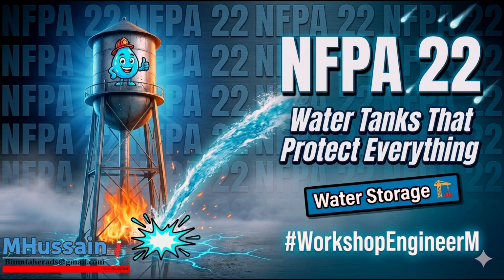Let's calculate the physical reality of that. Okay. If you take the coefficient of thermal expansion for carbon steel, and you have a 100-foot vertical discharge pipe exposed to a 100-degree temperature swing throughout the year, that pipe is going to physically grow and shrink by roughly 3/4 of an inch. 3/4 of an inch of linear expansion sounds small, but the forces generated by that thermal expansion are immense. Right, because it's solid steel.